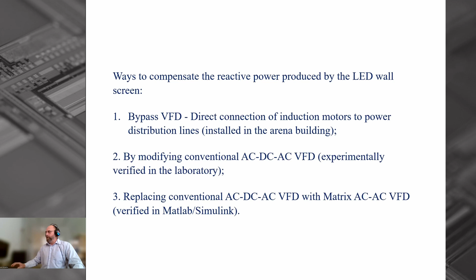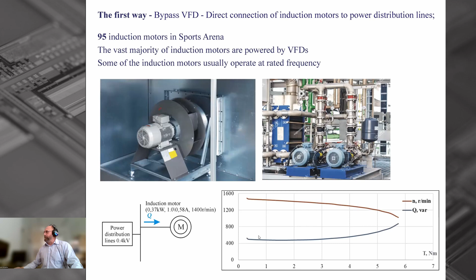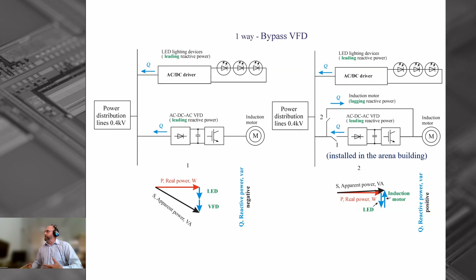So why does the first way of compensation work? Because there are a lot of induction motors installed in the sport arena. They are used for fan powering and pump powering, and all the induction motors produce positive reactive power. By bypassing the variable frequency drive and connecting the induction motor directly to the power distribution line, the induction motor could compensate the reactive power produced by the LED lighting devices and bring the power factor close to 1, and the reactive power close to 0.